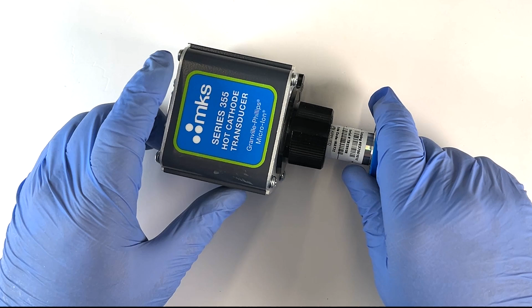Before beginning the procedure, turn off the power supply and then disconnect power from the transducer. Vent the vacuum chamber to atmospheric pressure and remove the module from the system. To remove the old gauge, grasp the knurled ring and firmly rotate counterclockwise to unlock the gauge. Pull the gauge straight out from the module.